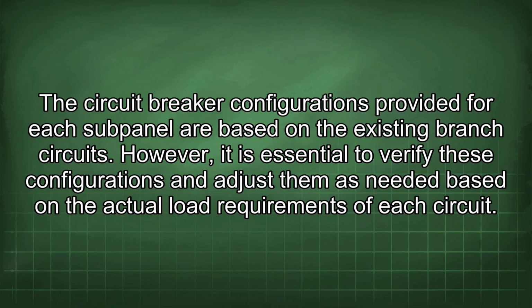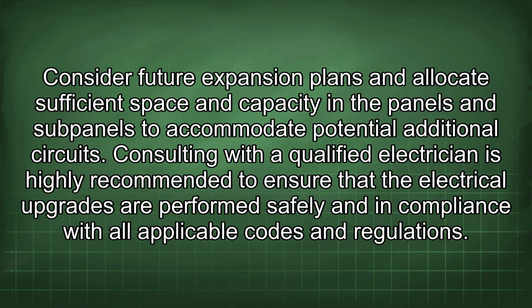The circuit breaker configurations provided for each subpanel are based on the existing branch circuits. However, it is essential to verify these configurations and adjust them as needed based on the actual load requirements of each circuit. Consider future expansion plans and allocate sufficient space and capacity in the panels and subpanels to accommodate potential additional circuits. Consulting with a qualified electrician is highly recommended to ensure that the electrical upgrades are performed safely and in compliance with all applicable codes and regulations.